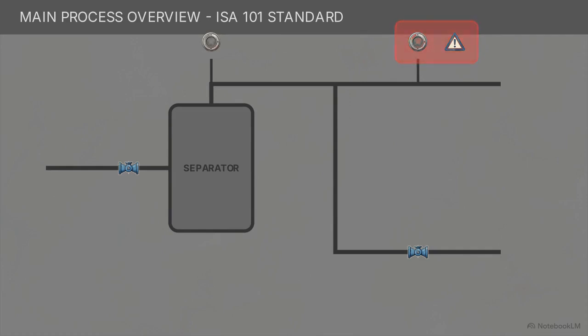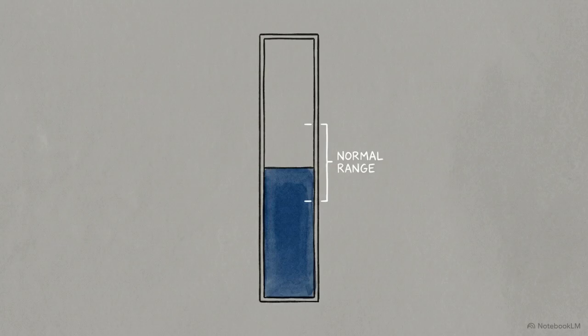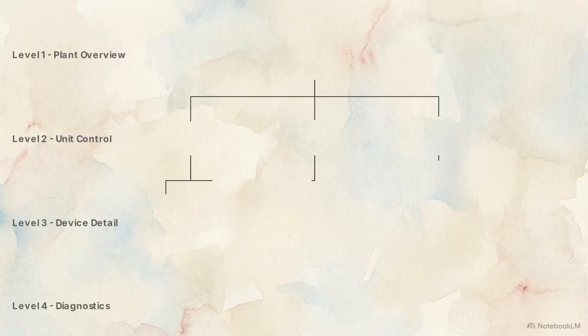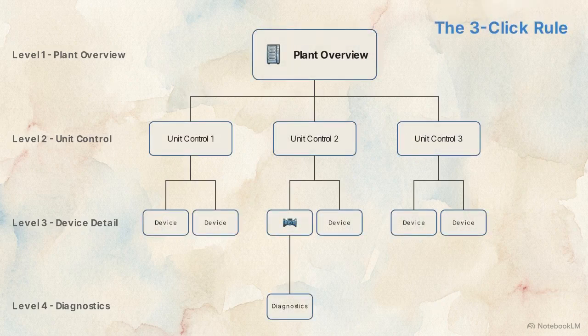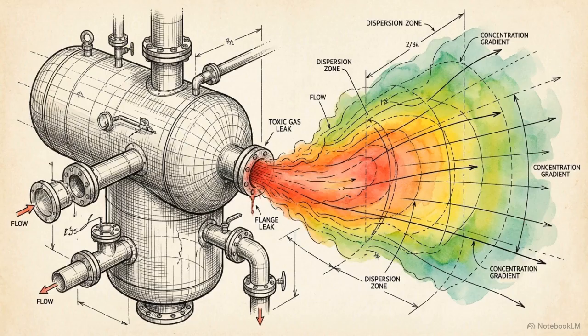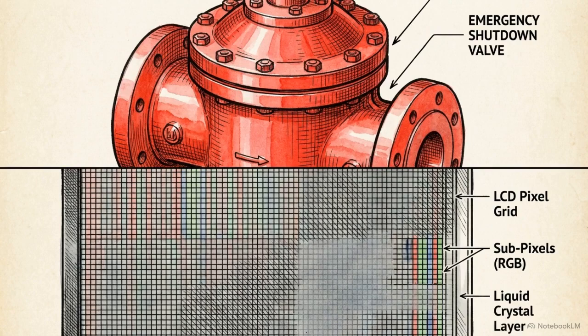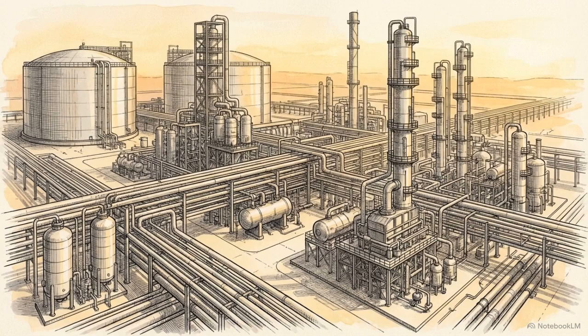Color is reserved exclusively for abnormal conditions, forcing the operator's eye to snap immediately to the only red element on the monitor. Raw data numbers are replaced with simple analog bar graphs that indicate process deviations at a glance, organized within a strict 4-level navigation hierarchy. To prevent fatal delays, the interface must follow the 3-click rule. An operator must be able to navigate from the top-level plant overview down to the specific diagnostic detail of any single component in 3 clicks or fewer. From calculating the fluid dynamics of a toxic gas cloud to isolating safety hardware, down to the exact shade of gray rendered on a monitor, true industrial safety is achieved by relentlessly engineering out every single point of human and mechanical failure.